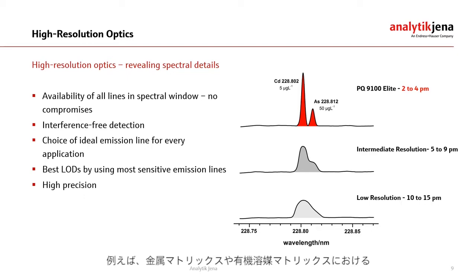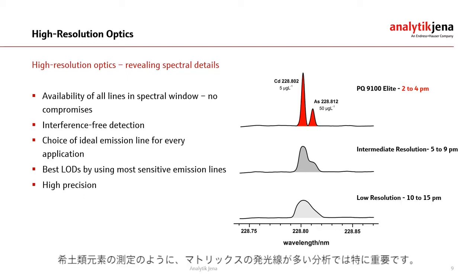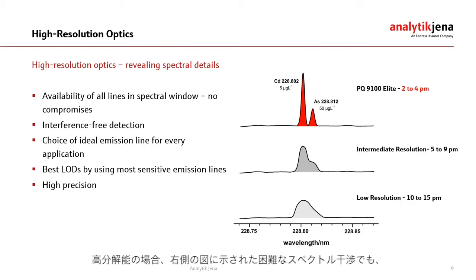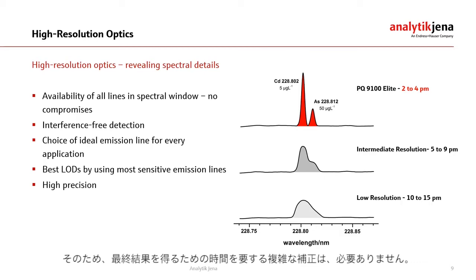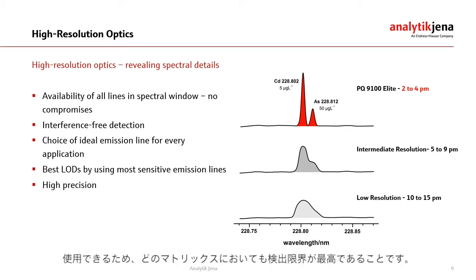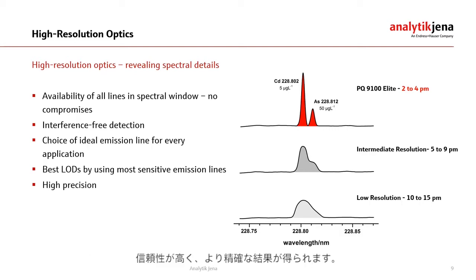High resolution is especially important for the analysis of line-rich matrices such as metal matrices, ore samples, rare earth element containing materials, or organic matrices. In these matrices, minor and main components cause numerous spectral interferences, making it necessary to employ elaborated correction algorithms. High resolution can provide interference-free detection of all elements even in these challenging matrices, as illustrated in the figure on the right. Additionally, the user does not need to employ time-consuming correction algorithms. Another main advantage is that you can use the most sensitive lines for your analyte, resulting in the best limits of detection in any matrix, giving you faster, more reliable and more precise results.